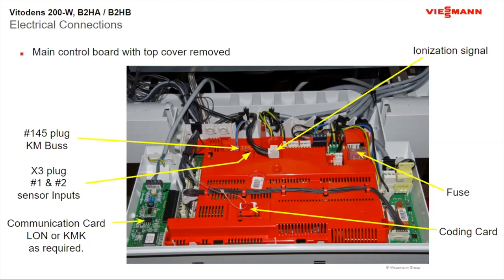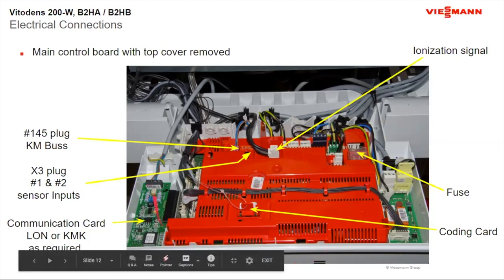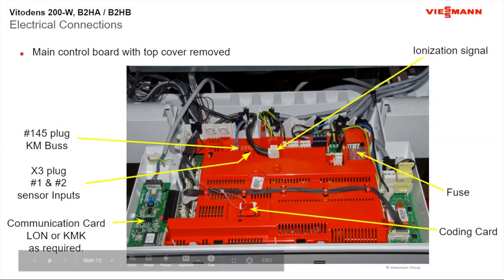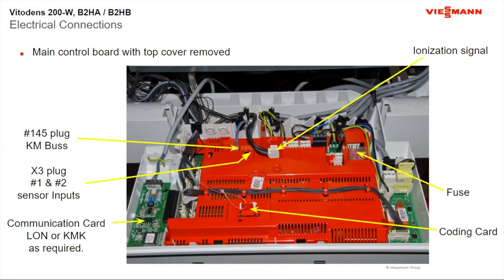Those sensors go to an orange plug. Right inside the control box there is a fuse — in the center of that plastic piece is a spare fuse. If you let the smoke out of the box, there's a spare fuse right there. Over here you would put your LON card. In this picture it shows KMK — that's Viessmann's communication protocol, used for thermostat-to-boiler and boiler-to-boiler communication on multiple boiler setups. Most systems now use LON communication for building management. We also offer a LON class as well as a multi-boiler hookup class.